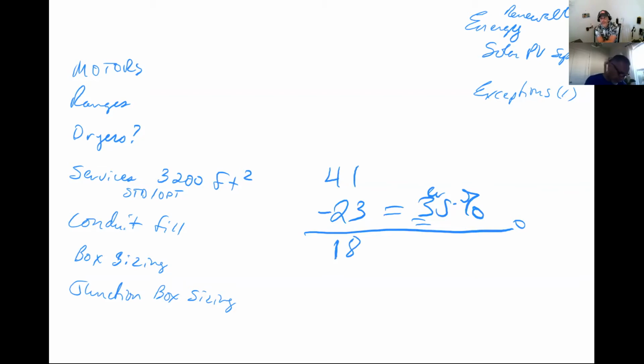Each one of those steps is only a 0.5% deduction instead of a full percent. So instead of 1%, it's 0.5% for each of those extra dryers, but it comes off the 35%, not the 47. So we take 35% minus 18 times 0.5, which is 9. That 9% is subtracted from the 35.